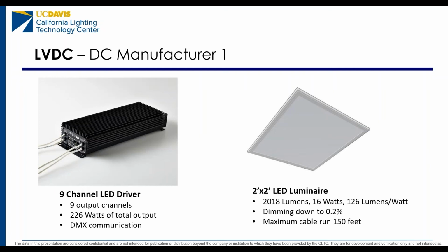For the low voltage DC system, we purchased this 9-channel LED driver. It has 9 output channels with a maximum of 226 watts of DC power. It communicates via DMX protocol. And as a load to this power supply, we procured 9 2x2 LED luminaires with 2018 lumen output at 16 watts, or 126 lumens per watt.